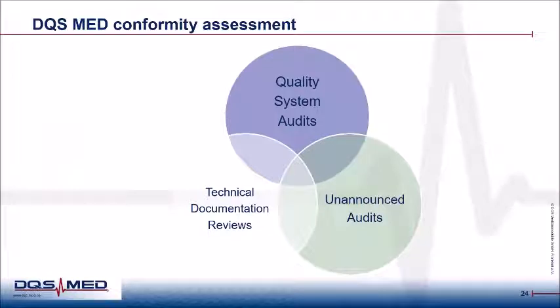We're still in the same approach if it's about the different parts. As we have heard, we have quality system assessments to do. Those quality system assessments have to be performed on site. We have technical documentation reviews for technical documentation to be done on site or off site. So this is up to the arrangement between the auditor, the assessor, and the company. If it is preferred to be done on site, then this can be done. If it's preferred to be done off site, this is also an option. And as already introduced with a recommendation back from 2013, we have unannounced assessments that have to be performed to a certain extent, depending on the risk classes of the medical devices you place into the market.